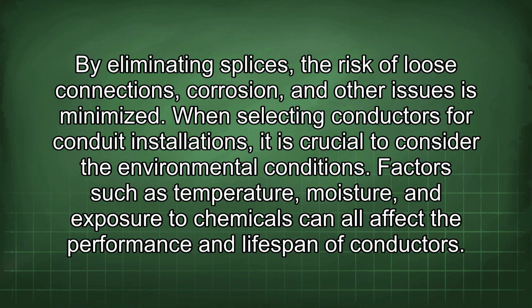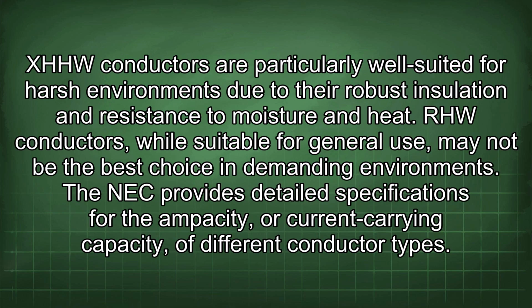When selecting conductors for conduit installations, it is crucial to consider the environmental conditions. Factors such as temperature, moisture, and exposure to chemicals can all affect the performance and lifespan of conductors. XHHW conductors are particularly well suited for harsh environments due to their robust insulation and resistance to moisture and heat. RHW conductors, while suitable for general use, may not be the best choice in demanding environments.